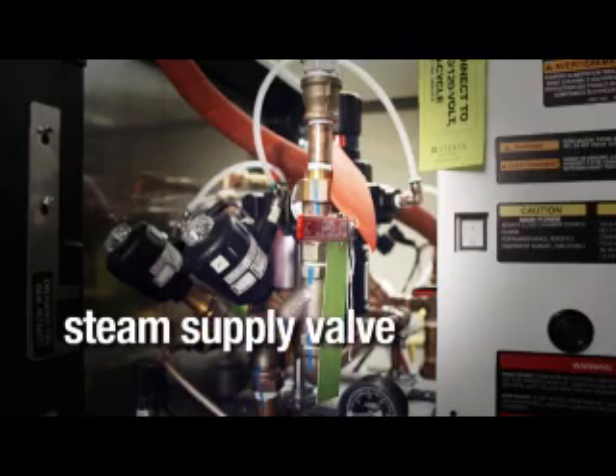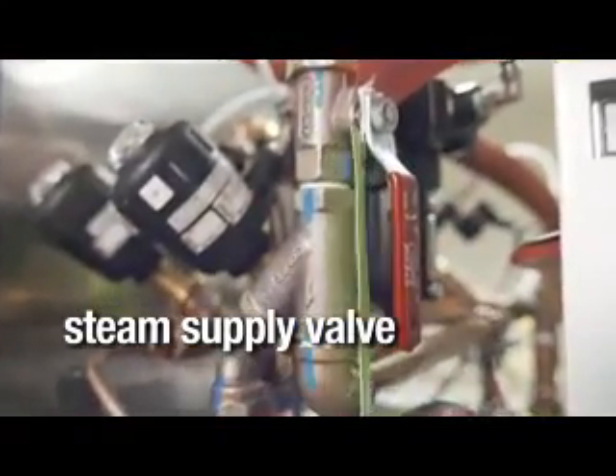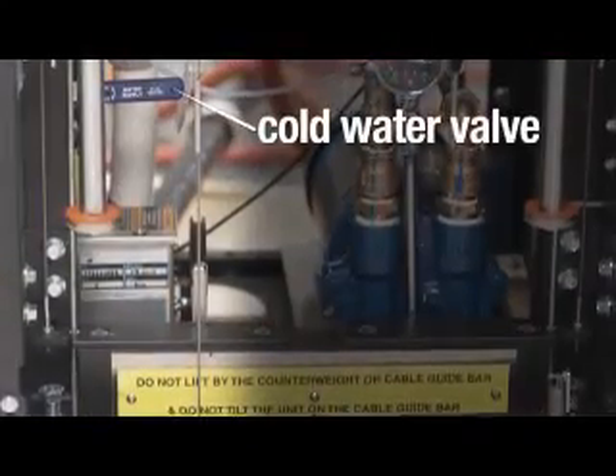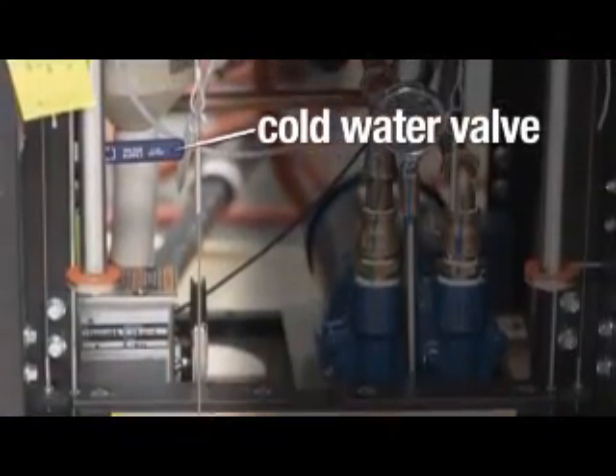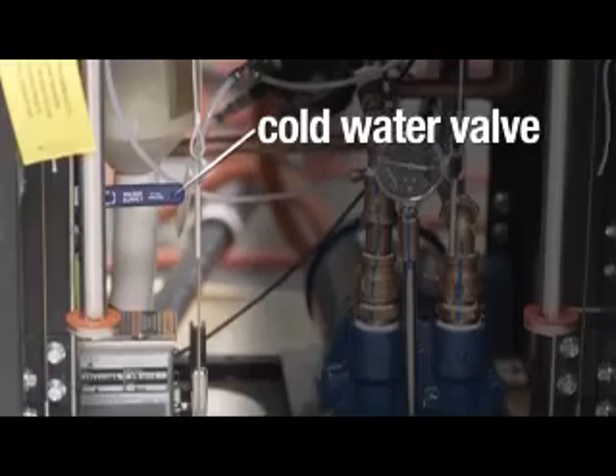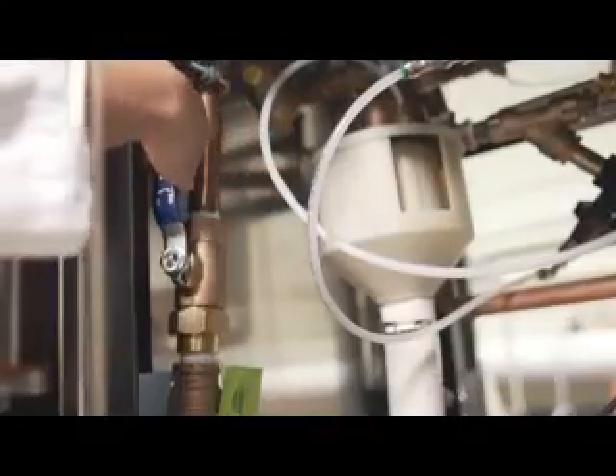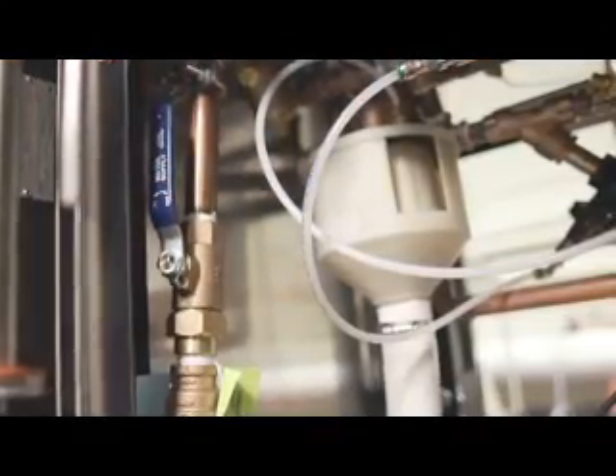The steam supply valve is located behind the front access panel above the chamber. Ensure this is in the open position before trying to operate the sterilizer. The water supply valve is located behind the front access panel below the chamber. Ensure this is in the open position before trying to operate the sterilizer.